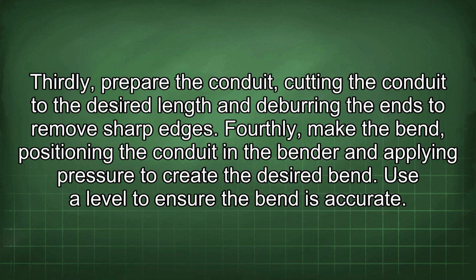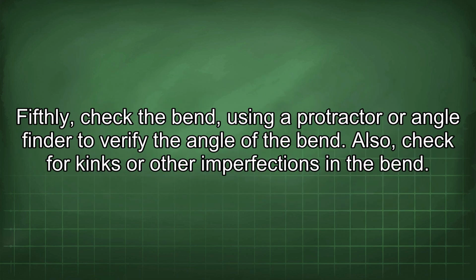Thirdly, prepare the conduit, cutting the conduit to the desired length and deburring the ends to remove sharp edges. Fourthly, make the bend, positioning the conduit in the bender and applying pressure to create the desired bend. Use a level to ensure the bend is accurate. Fifthly, check the bend, using a protractor or angle finder to verify the angle of the bend. Also, check for kinks or other imperfections in the bend.